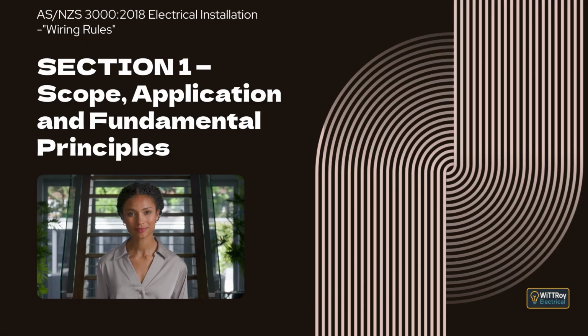Clause 1.5.10, Protection against earth fault currents. Any earthing conductor, and any other part of the system that must carry an earth fault current, must be capable of carrying that current without being damaged. This ensures the protective device can operate safely during an earth fault. Clause 1.5.11, Protection against abnormal voltages. This clause covers protection against harmful effects of abnormal voltages. These can come from several sources: faults between live parts of circuits supplied at different voltages, induced voltages in unused conductors, or harmful influences between different circuits and installations.